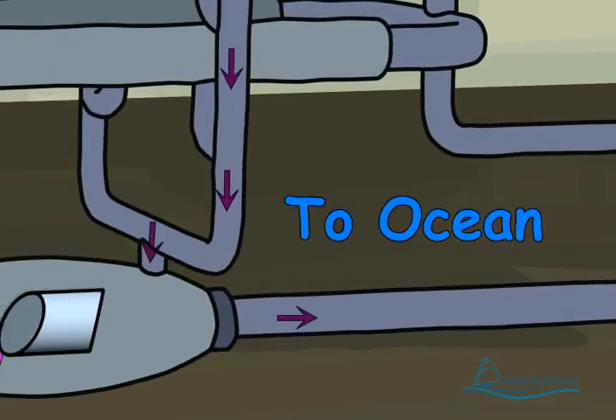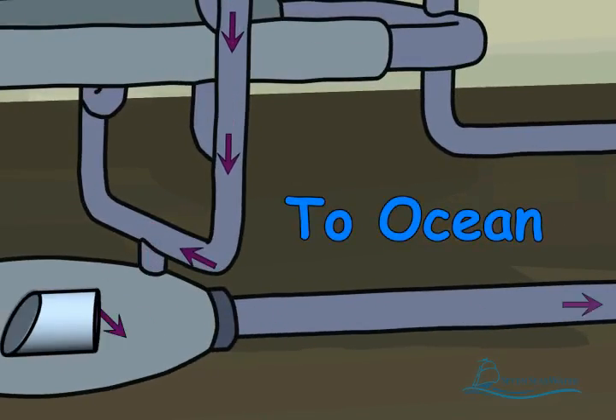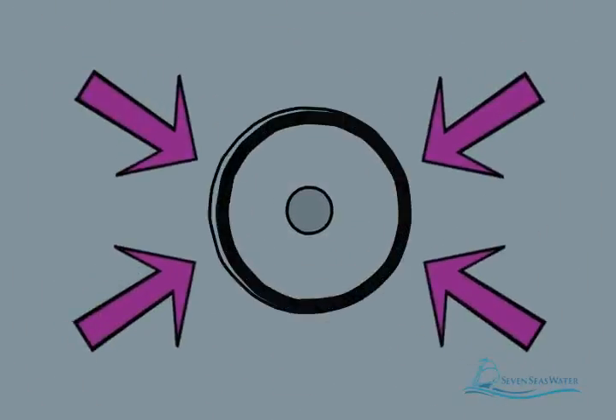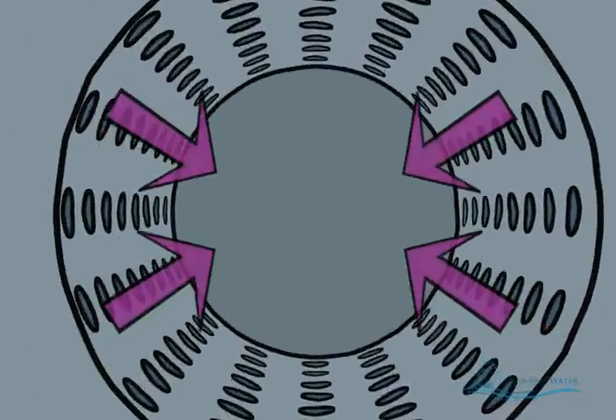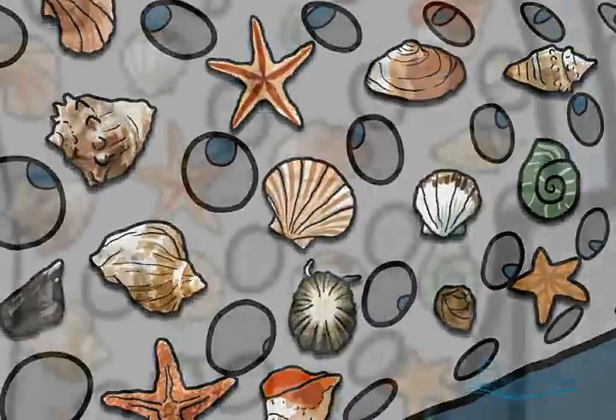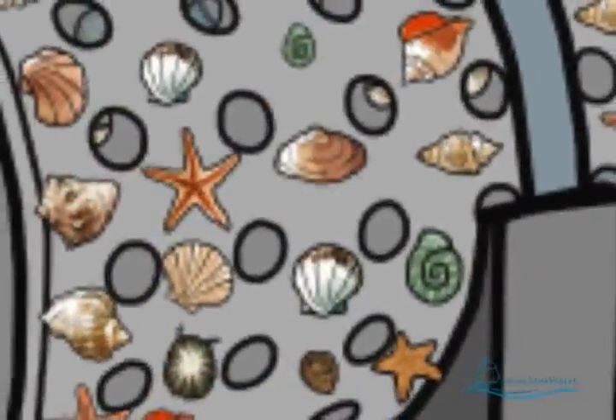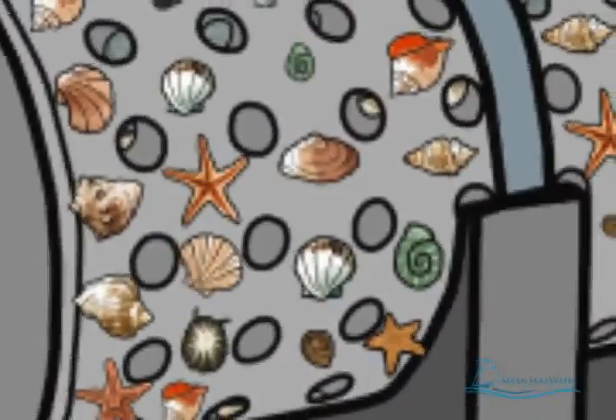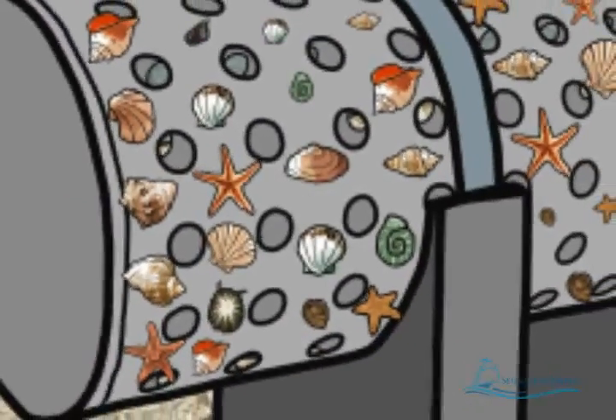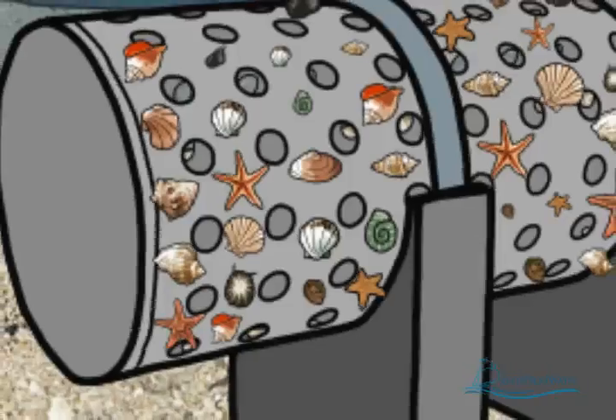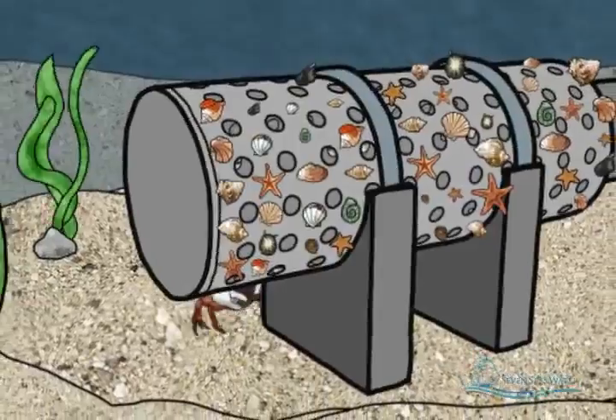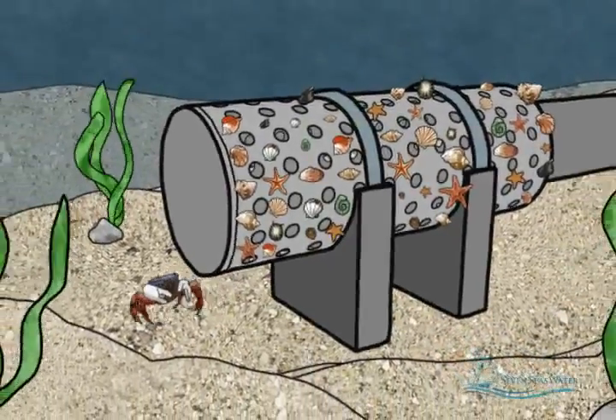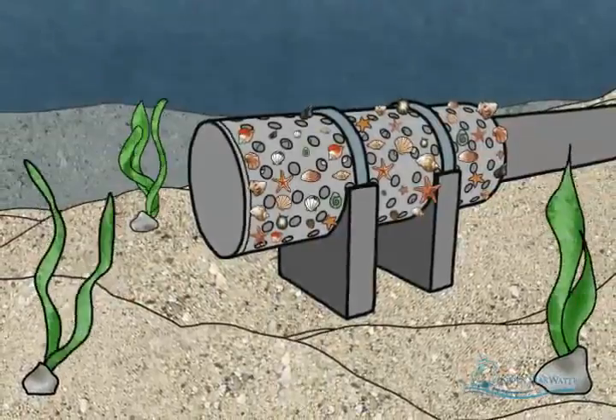The concentrated salt stream will have about a 60% higher salinity than the incoming seawater. The concentrated salt stream is sent back to the ocean through a brine disposal well, or a device known as a brine outfall. The brine outfall is situated in an area of significant ocean flow so that the salt levels are quickly returned to equilibrium with the ocean. The location for the outfall should contain no sensitive marine ecosystems. In a properly designed brine outfall, no noticeable increase in salinity can be detected at a distance of a few meters from the discharge.